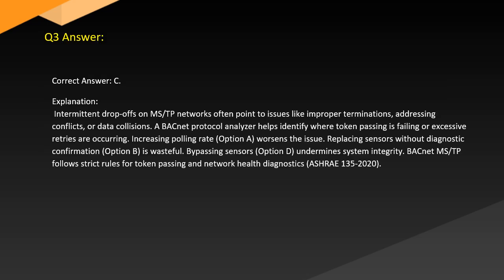Answer. Correct answer: C. Explanation. Intermittent drop-off on MS/TP networks often points to issues like improper terminations, addressing conflicts, or data collisions. A BACnet protocol analyzer helps identify where token passing is failing or excessive retries are occurring.